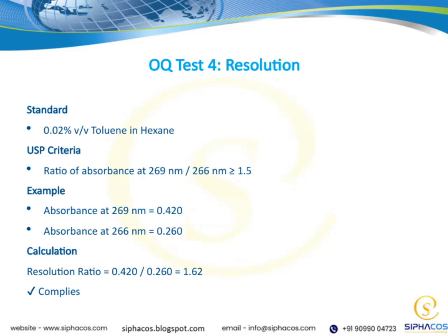All right, let's look at OQ Test 4, which focuses on resolution. The standard here is quite specific. We're looking at a 0.02% v/v toluene in hexane solution. Now, the key criterion set by the USP is that the ratio of absorbance at 269 nanometers to 266 nanometers should be at least 1.5. What does that mean in practical terms? Well, it's about how well we can distinguish toluene from other components based on their absorbance at these two wavelengths.